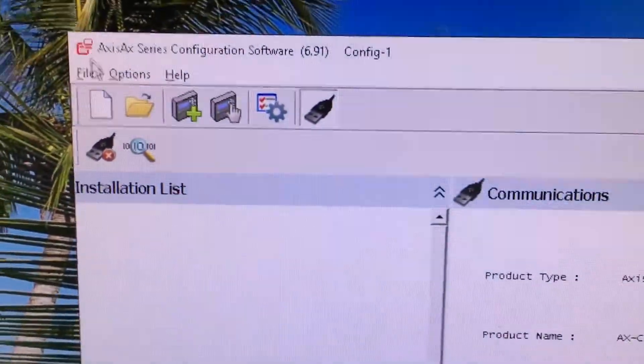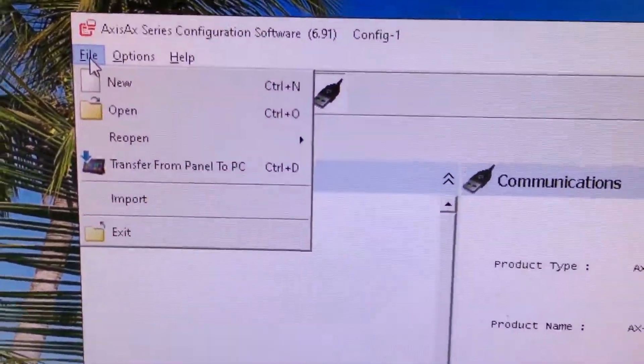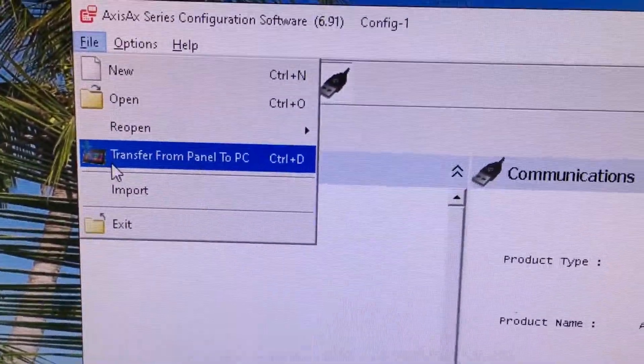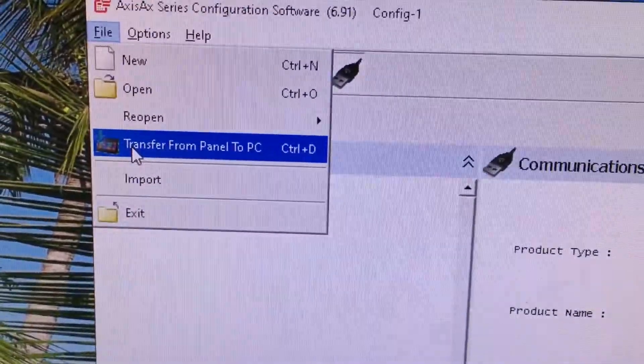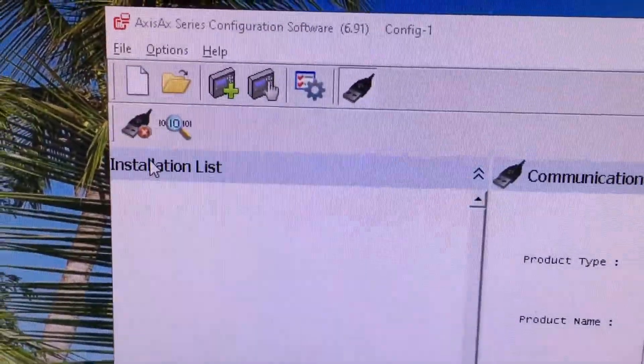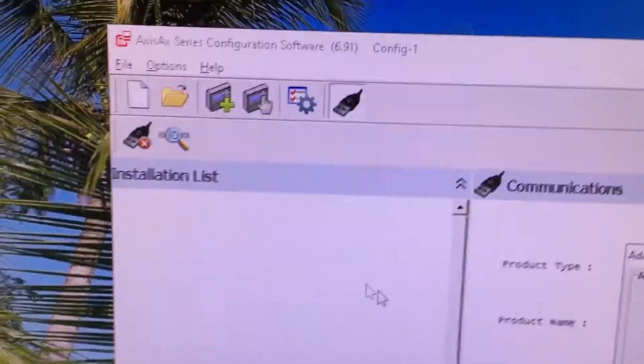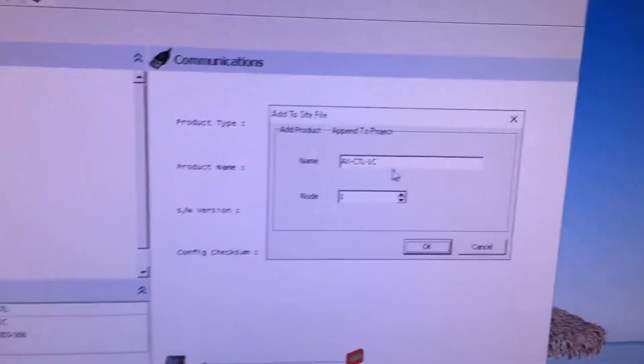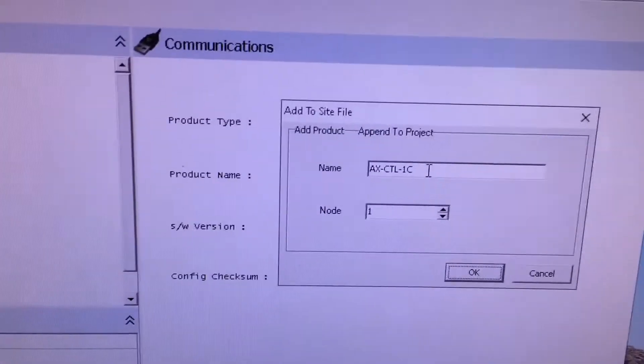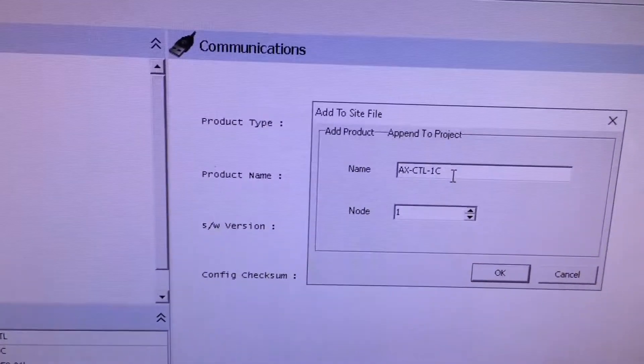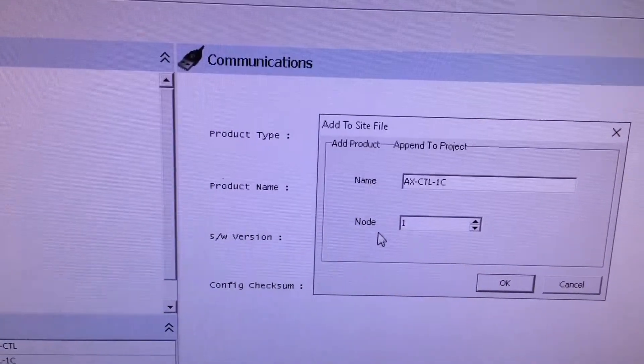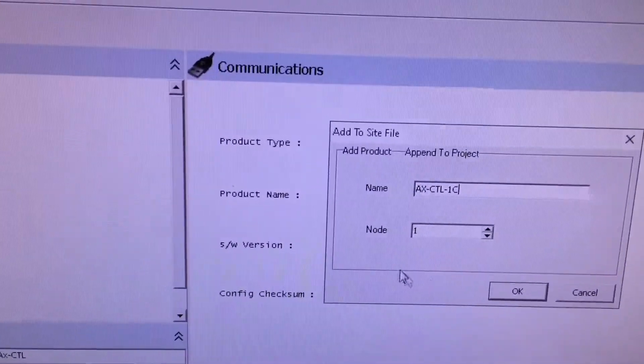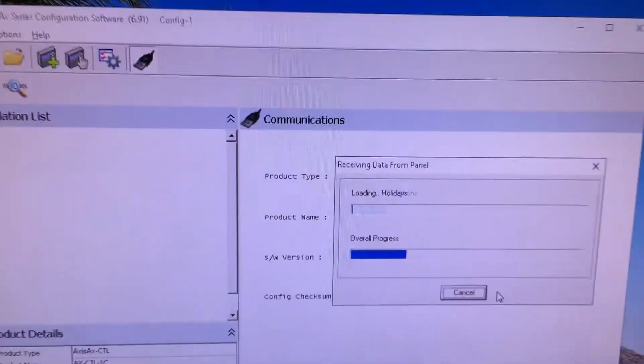Our next step is that we're going to click on the word File, and this is the only time that you will see this. We're going to click on File and you'll see that there's an option here that says Transfer from Panel to PC. We shall select that. What it's going to do is ask us to give it a name and whether it's a standalone panel. We'll just leave it as an AXCTL1C with a label. It is node number one because I have an annunciator on this system, and I'll say okay.